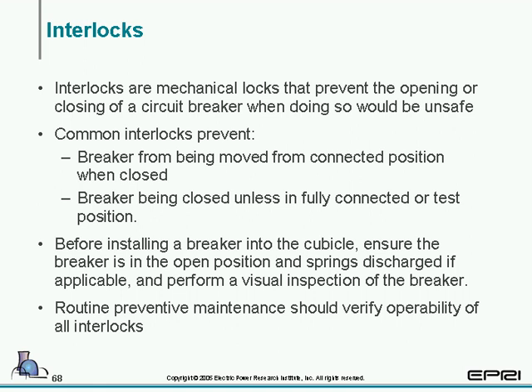Before installing a breaker in the cubicle, ensure the breaker is open and springs are discharged, and perform a visual inspection of the breaker before installing it. And of course, your routine PM procedures should verify the operability of all interlocks. We discussed that last week. Keyed systems. It's very important to ensure proper control of keys of keyed systems. If you have duplicate keys, they should be put in a safe place and only accessible to authorized personnel.